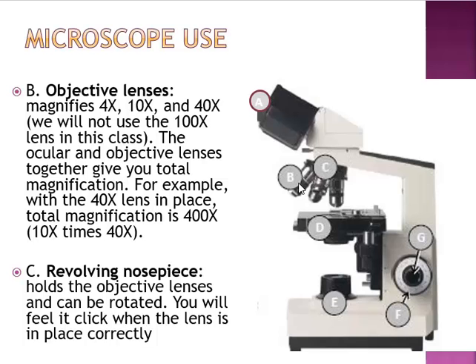When you're looking through your ocular lens at your lowest power objective, which is your 4 times, you are actually looking at 40 times the total magnification, because you have 10 times and 4 times. That's 40 times. If you were looking at the mid power, which is 10 times, you would have 10 times 10, which is 100 times the normal magnification that you would see with your eye. And last, if we were looking at the highest power in this case, we would have 10 times the 40 times, which is 400.